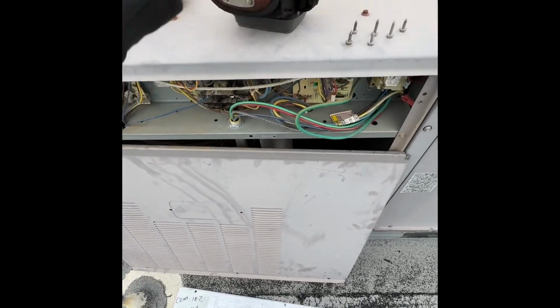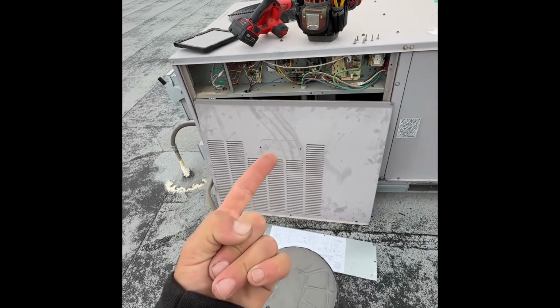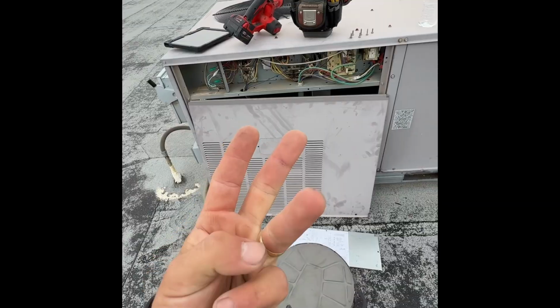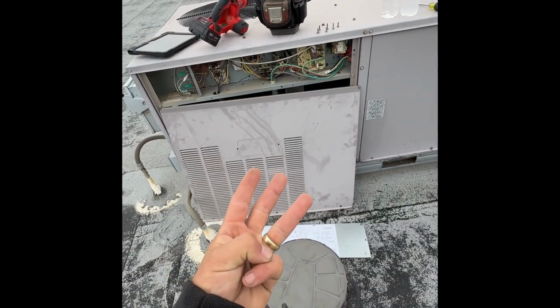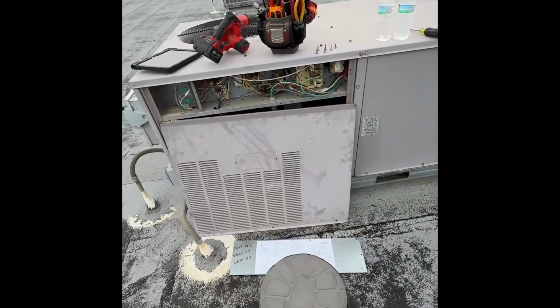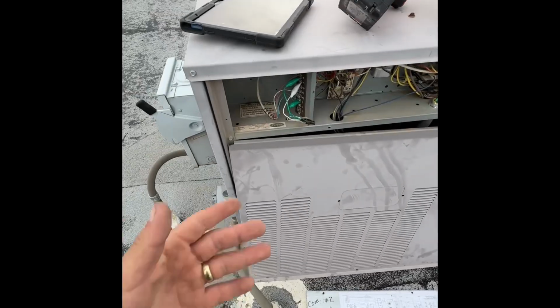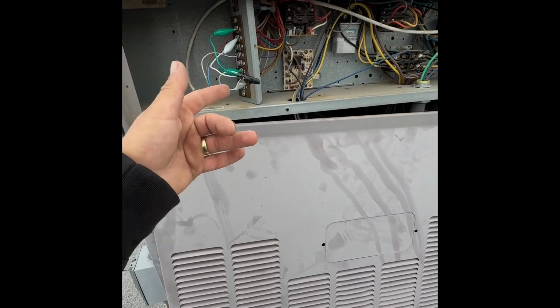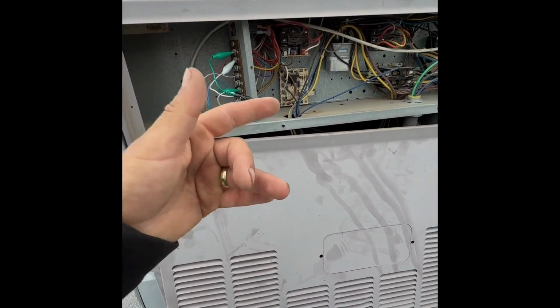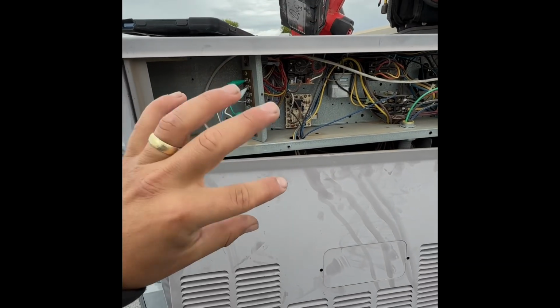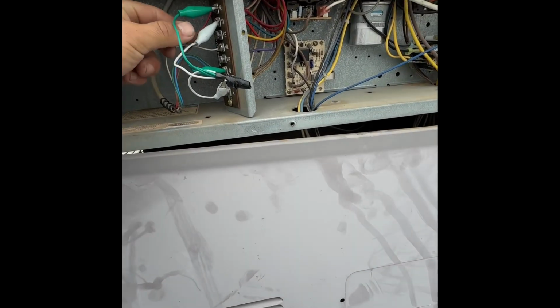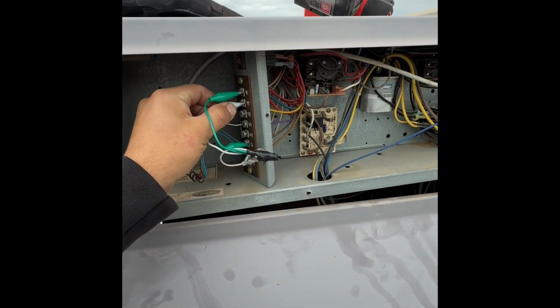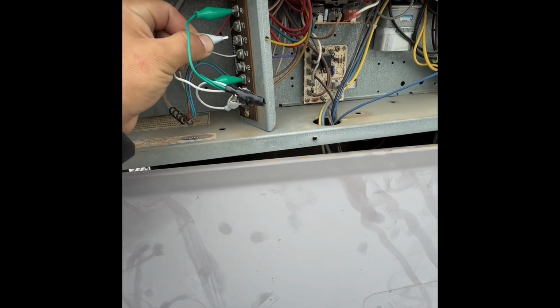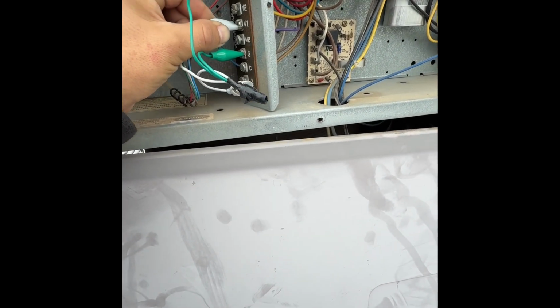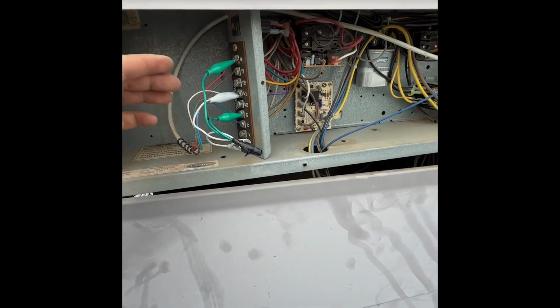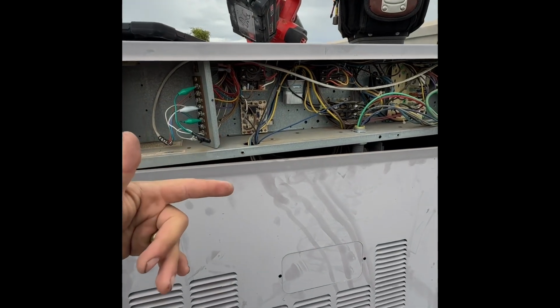So there we go. We covered amp draws, we covered outdoor fan motor, we covered indoor blower motor, we covered temperature splits, and we covered how to get the unit to do what you want it to do from the rooftop. So now let's switch it over to heating so you guys can see how that works. Some heat pumps are different than others. So let's just try moving the yellow from there to here. There you go. You heard the reversing valve switch over.